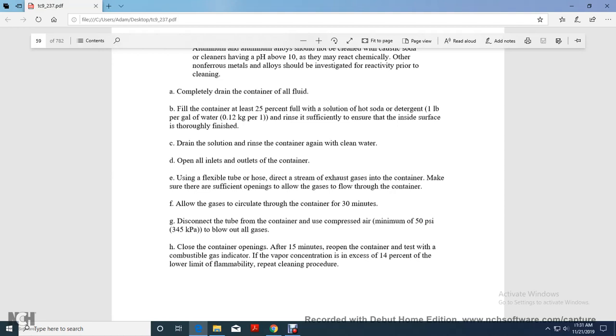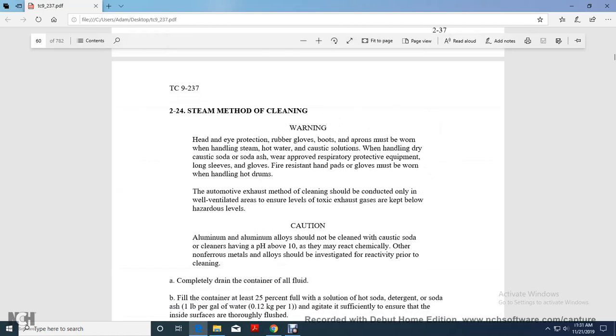Open all outlets of the container. Using a flexible tube and a hose, direct a stream of the exhaust gas into the container. Make sure there is sufficient opening to allow the gas to flow through the container. Allow the gas to circulate through the container for 30 minutes. Disconnect the gas tube from the container and use compressed air at a minimum of 50 psi to blow out all gases. Close the container opening after 15 minutes. Reopen the container and test with the combustible gas indicator. If the gas vapor concentration is in excess of 14% of the lower flammability limit, repeat the cleaning procedure.